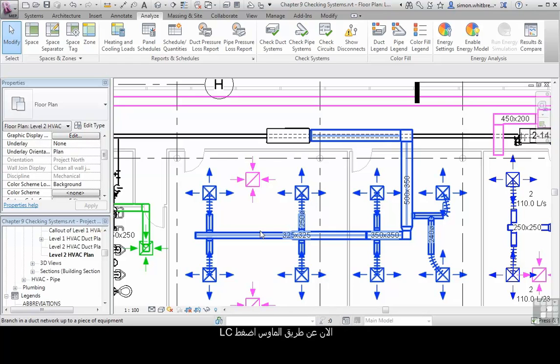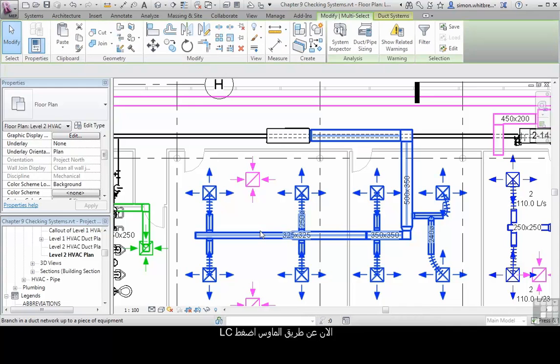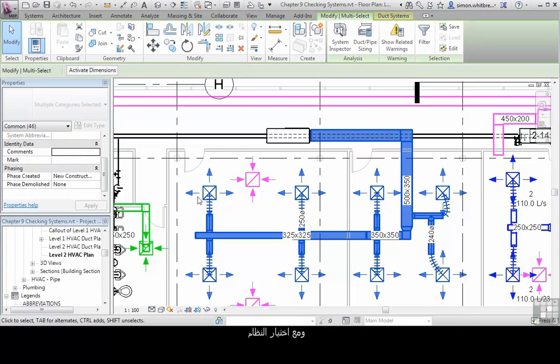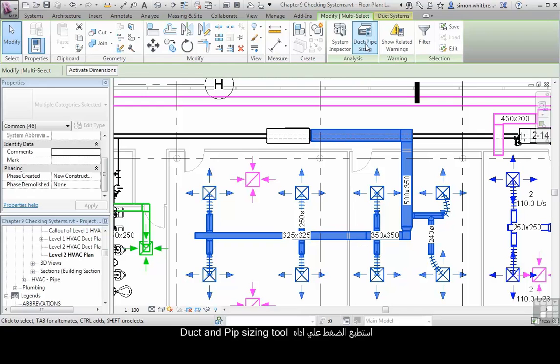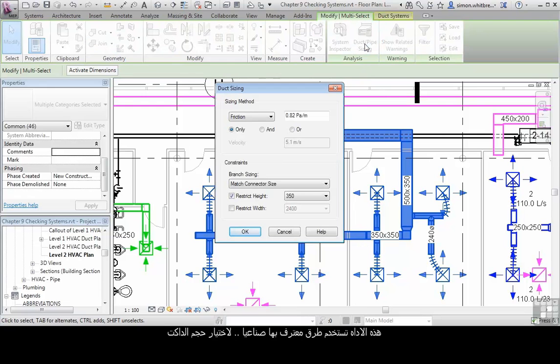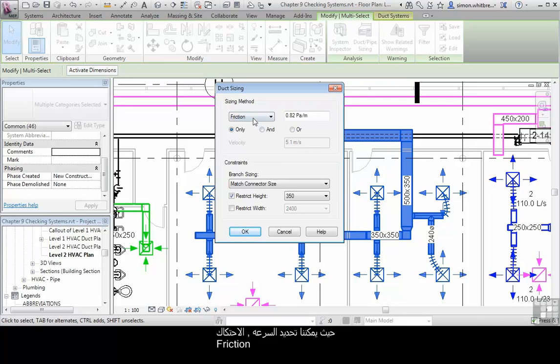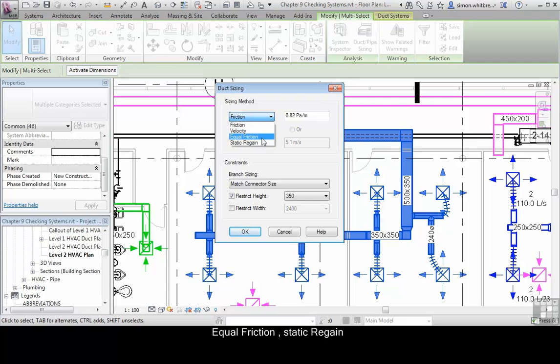Now I can select with my left mouse click, and with the system selected, I can click on duct and pipe sizing. This tool uses industry recognized methods for sizing ducts, where we can specify velocity, friction, equal friction, or static regain methods.